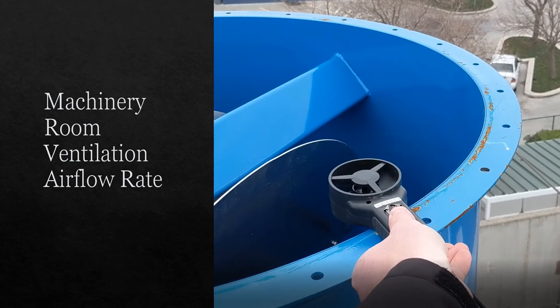Similarly, emergency ventilation need not be activated until 1000 PPM — IIAR Standard 2 requires ventilation to be activated at 150 PPM. The machinery room ventilation emergency airflow rate is established by the requirement at the time the machinery room was built or modified; 30 air changes per hour is not required in Standard 9. The biggest implication of Standard 9 is the requirement to perform a minimum system safety evaluation every five years, with the initial evaluation due in March 2025.